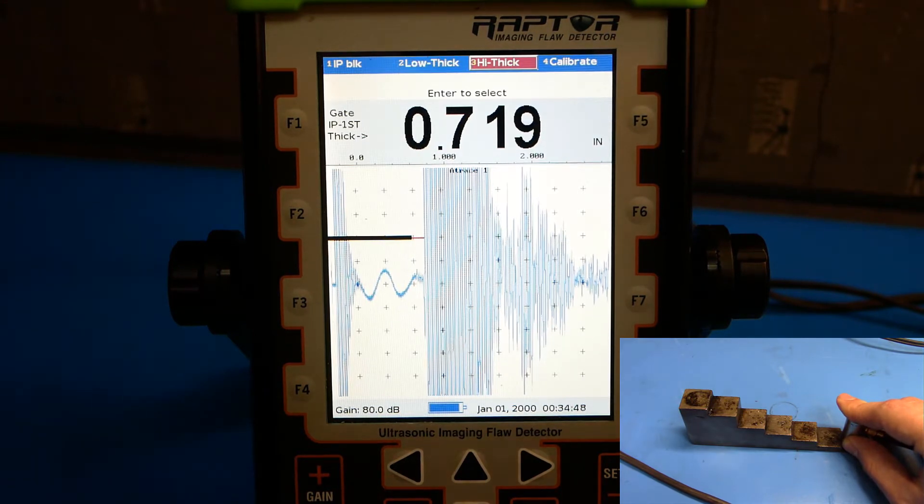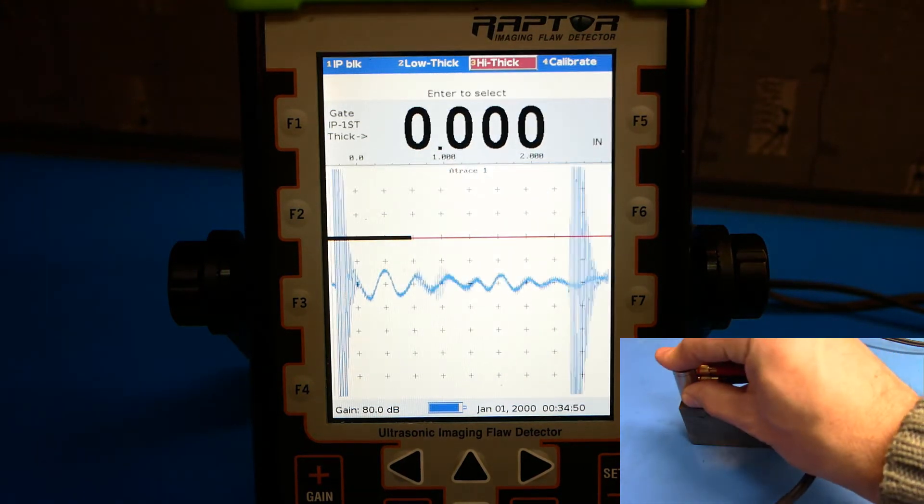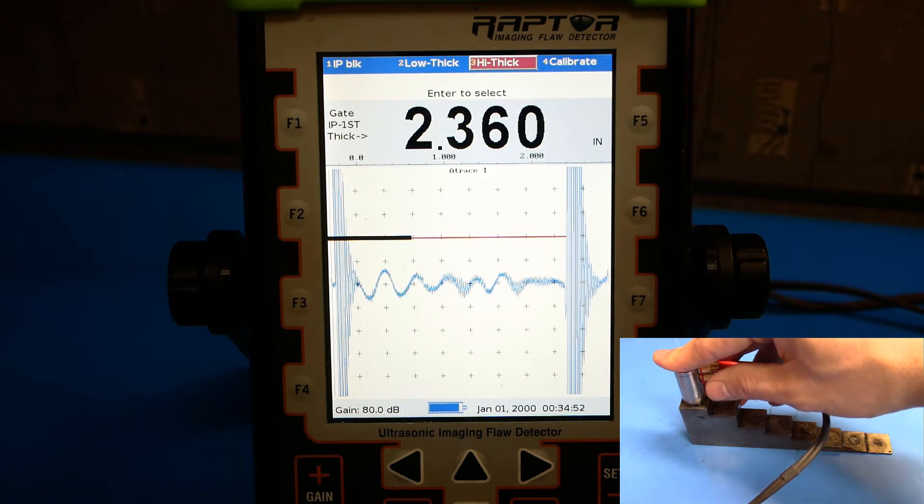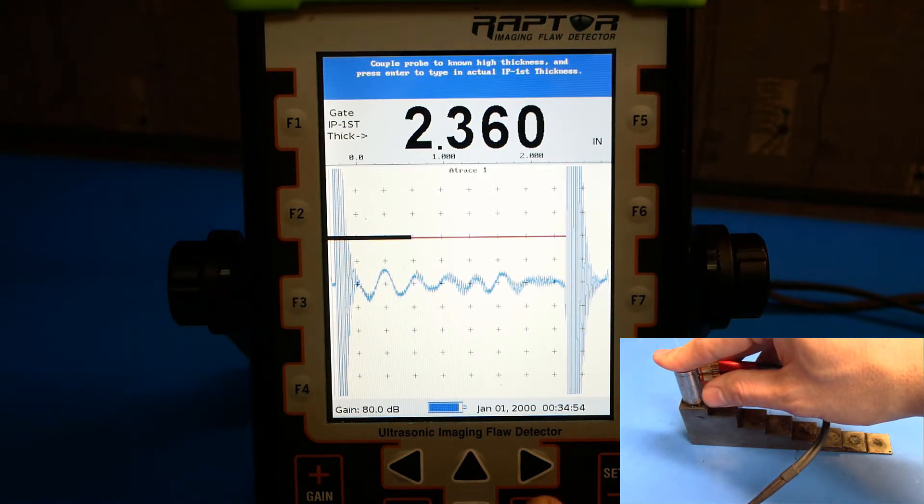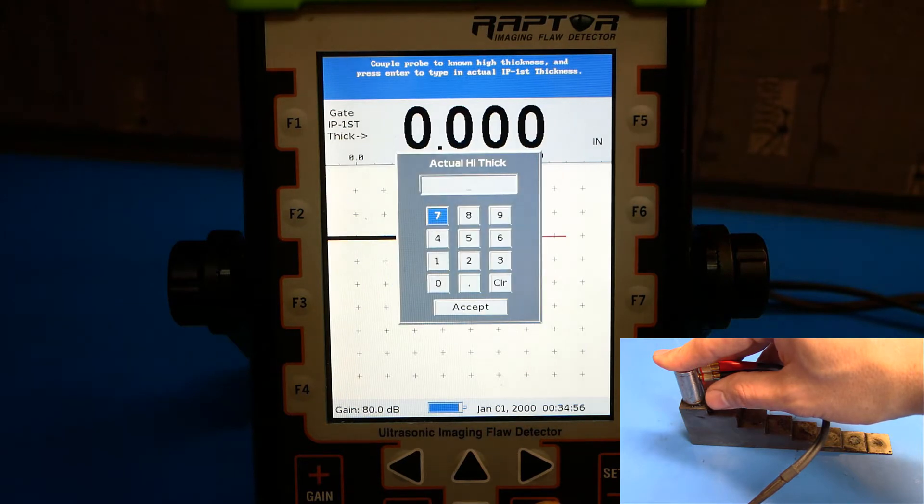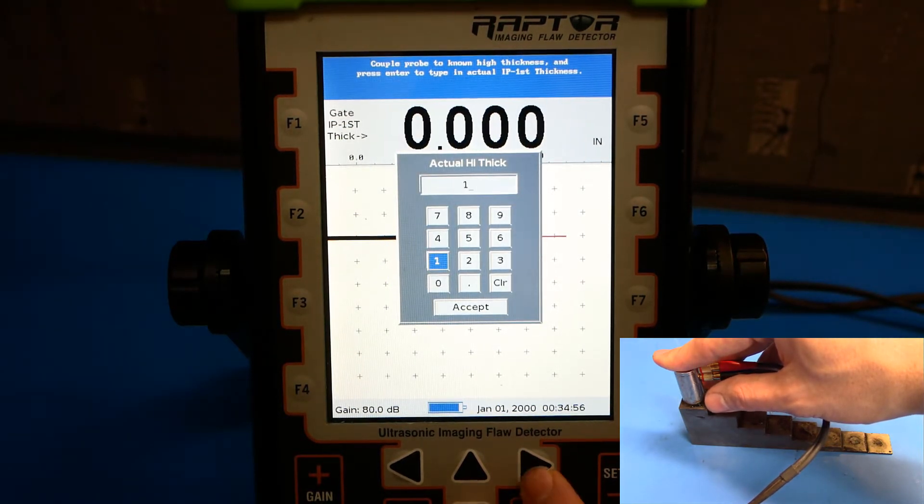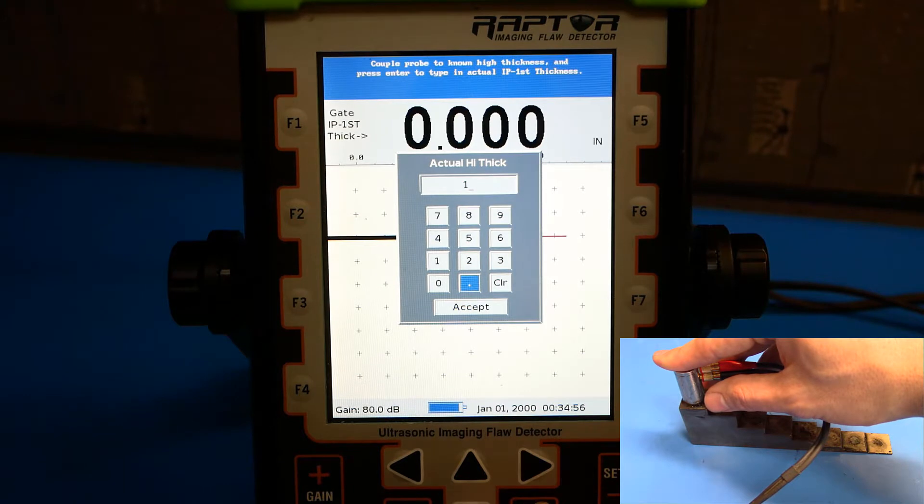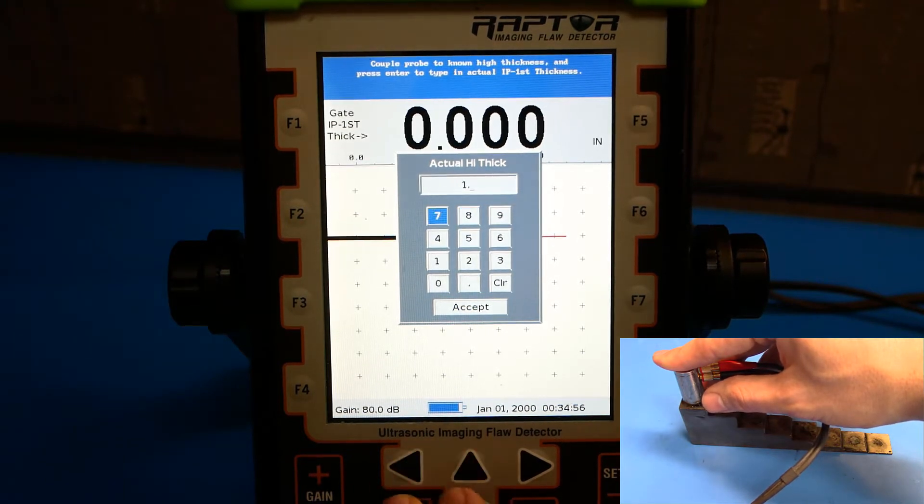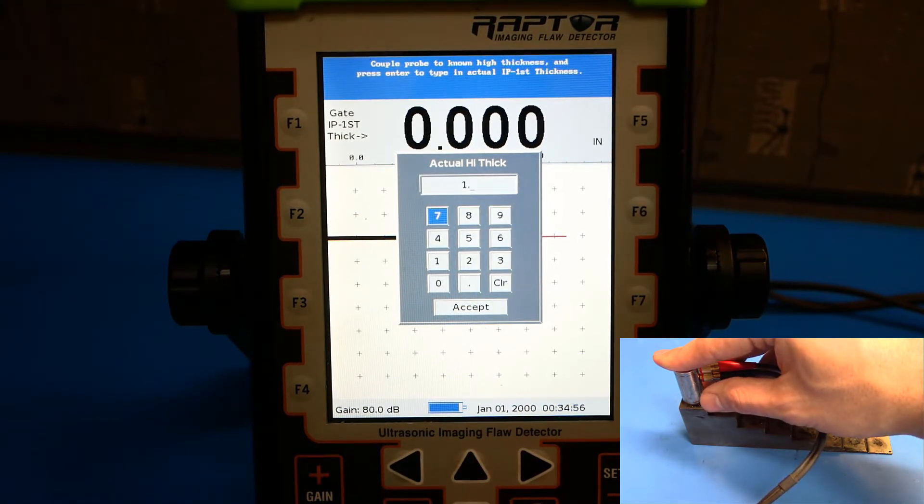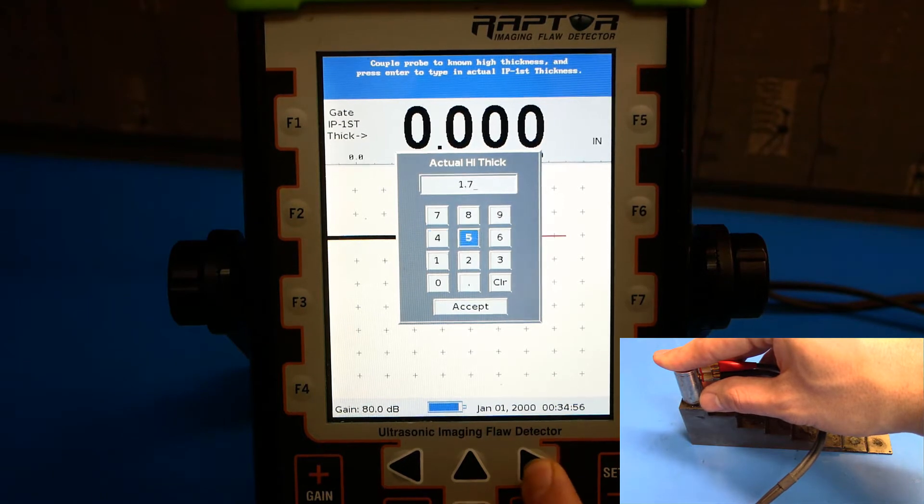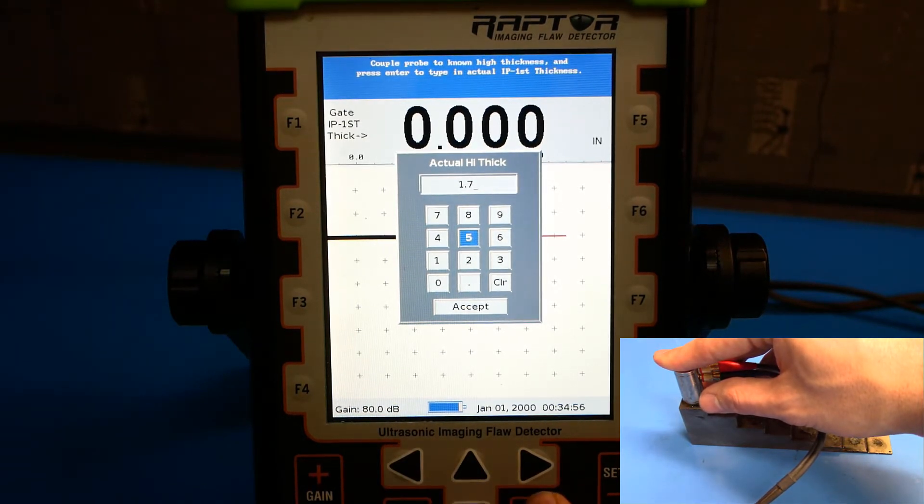Next, navigate to high thickness and couple to the high thickness on your step block. Push enter. Enter again. And enter 1.75 inches. Again, these are the values for my step block. If your step block has different values, use those values.